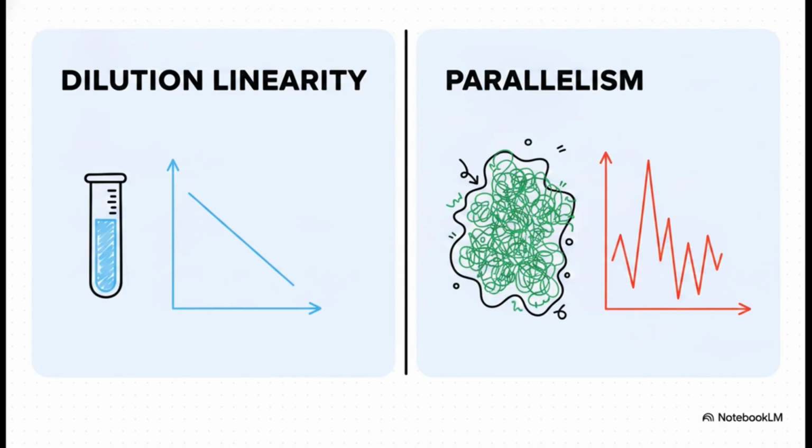Okay, so let's dive right into this by drawing a really hard line between dilution linearity and true parallelism failure, because it's such a common trap to confuse the two. Dilution linearity usually just tests whether a spiked sample, which is already way above your quantitative range, can be diluted back into range accurately. But parallelism? Parallelism asks a much harder question. It asks whether authentic, incurred samples, with all of their chaotic endogenous complexity, respond proportionally as they're diluted. The absolutely crucial point here is that your method can easily pass spiked dilution experiments with flying colors, but still completely fail when endogenous matrix components alter your analyte capture or detection. Passing a spiked sample is just not going to save you from real-world matrix interference.